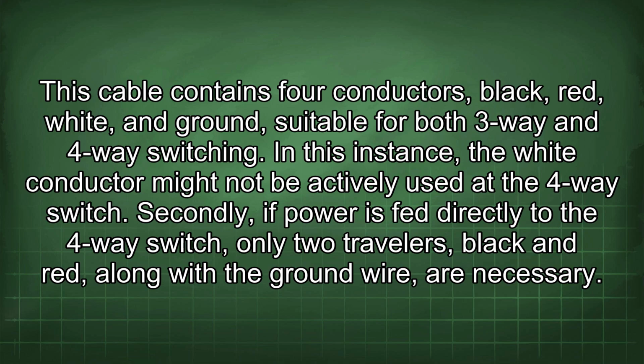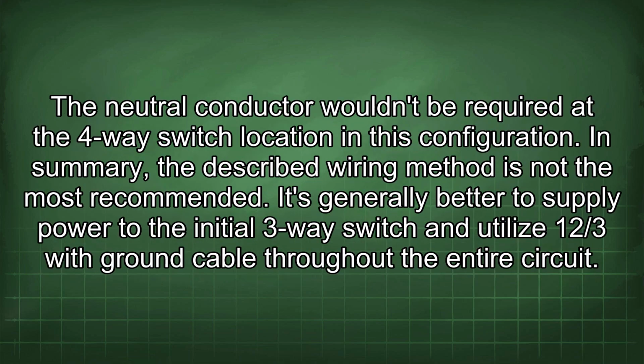Secondly, if power is fed directly to the 4-way switch, only 2 travelers, black and red, along with the ground wire, are necessary. The neutral conductor wouldn't be required at the 4-way switch location in this configuration.